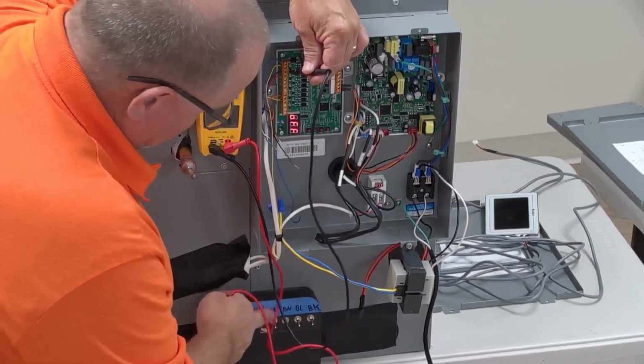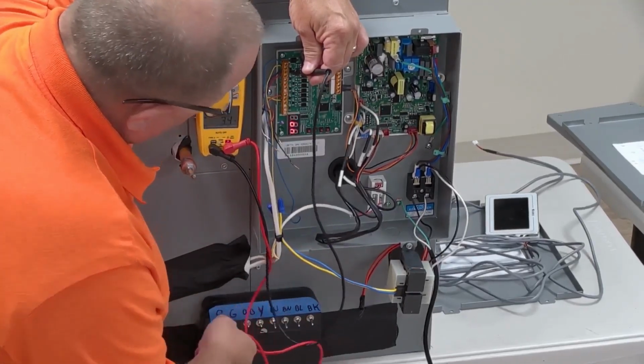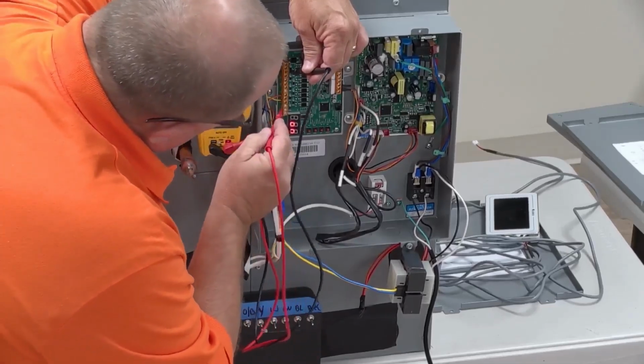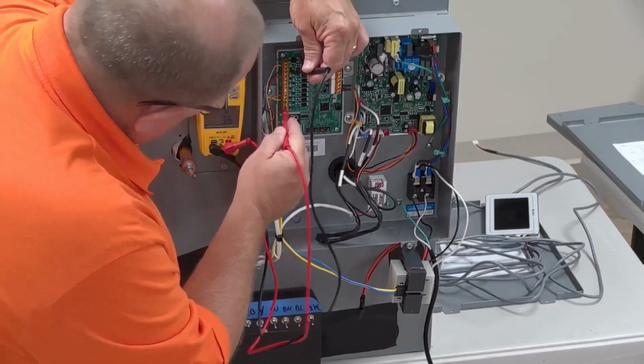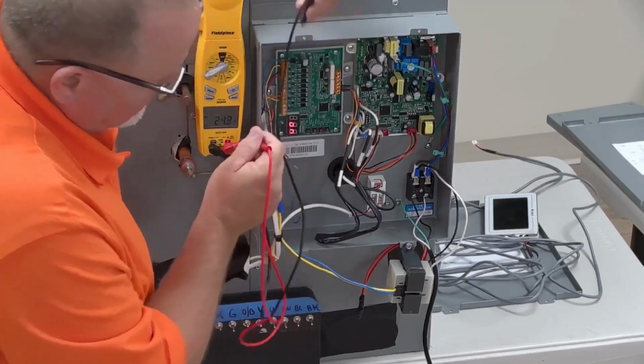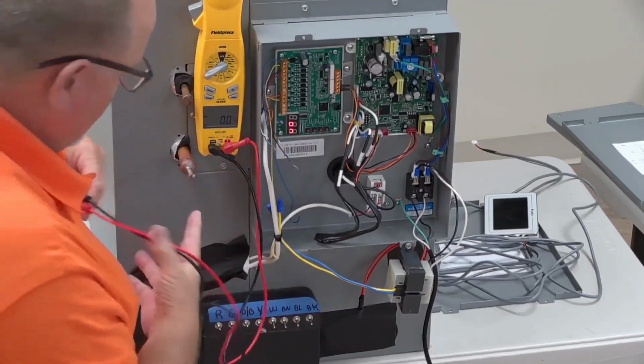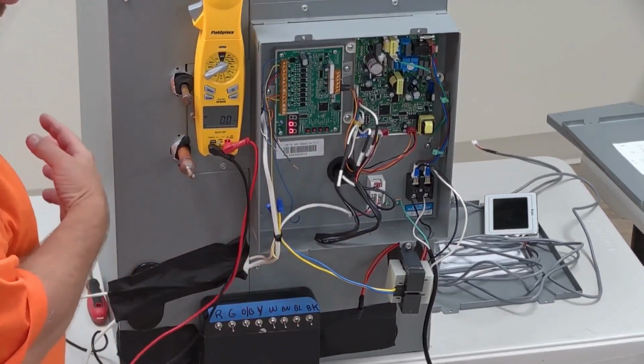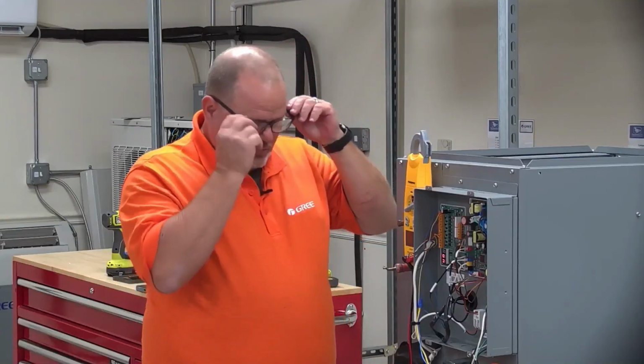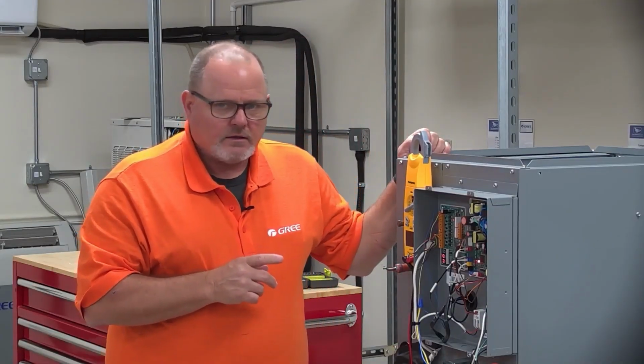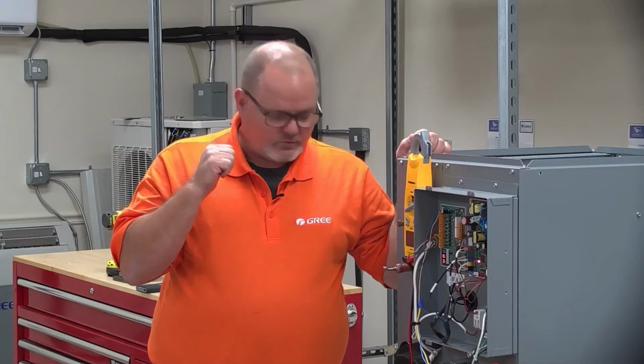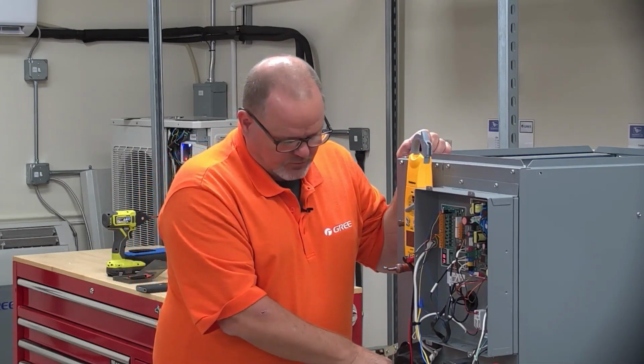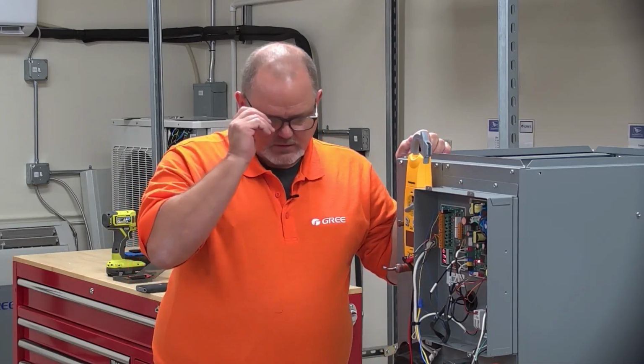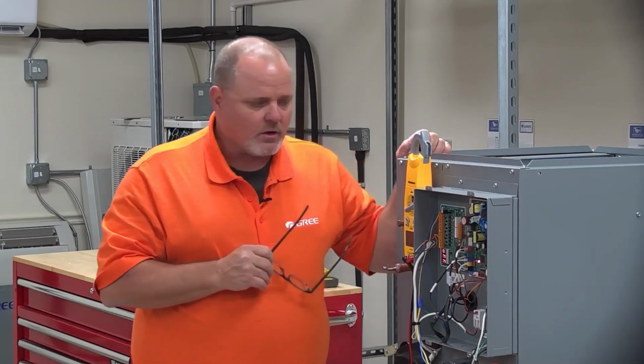And then if I get a heat pump call, which I'll go ahead and give it, just turned on, I've got 24 volts to Y. We don't have it on camera, and I don't have it refrigerantly piped, so I'm not going to leave it on more than a couple seconds, but I just turned on the condenser we tied it to. So I do have it tied to a MultiPRO Ultra, but I don't have it piped yet, and I don't want to leave it on.